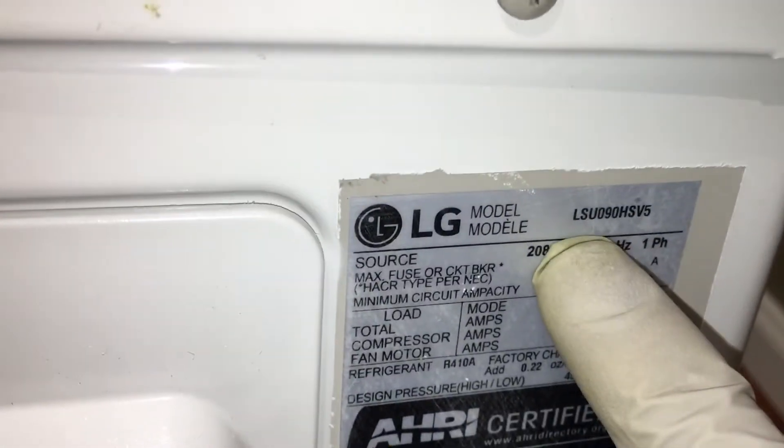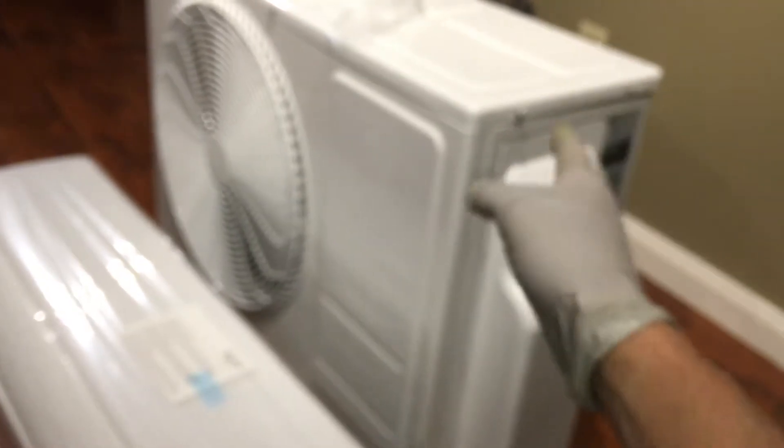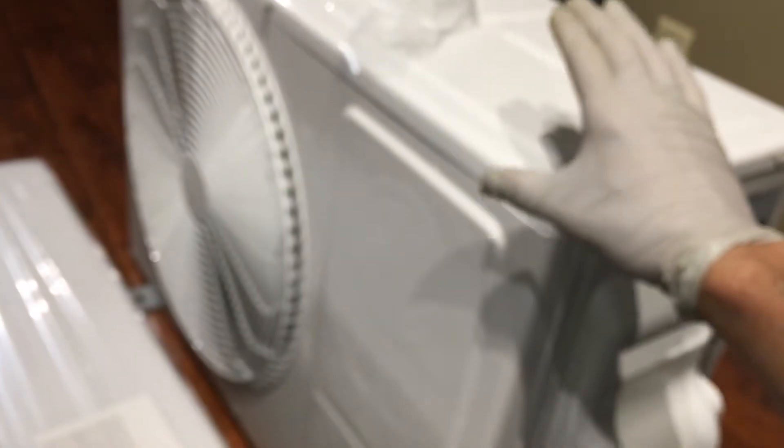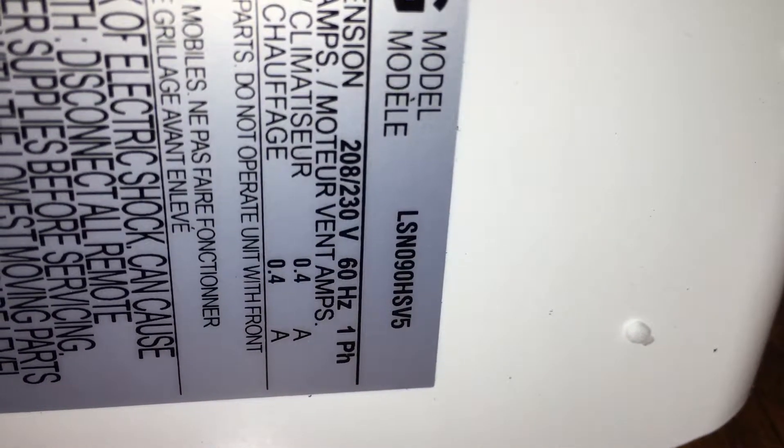The outdoor unit model number is LSU 090 HSV5, and that goes with the corresponding indoor head unit. You have to match them to get the correct efficiency, SEER rating, or EER rating. The indoor unit model number is LSN 090 HSV5. If it doesn't say that part number, you will not get the efficiency from the matching outdoor unit — they have to match.